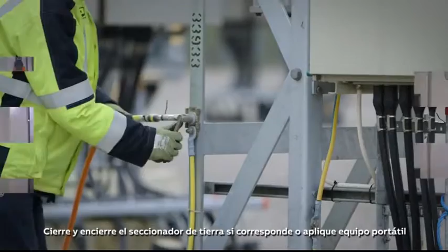Step 5. Carry out earthing and short-circuiting. Close and lock earthing switch if applicable, or apply portable equipment for earthing and short-circuiting while wearing the proper PPE identified in Step 1. Also, use insulated tools when required. Be sure the equipment is free of any residual charge or induced voltages and short-circuit any fault current.